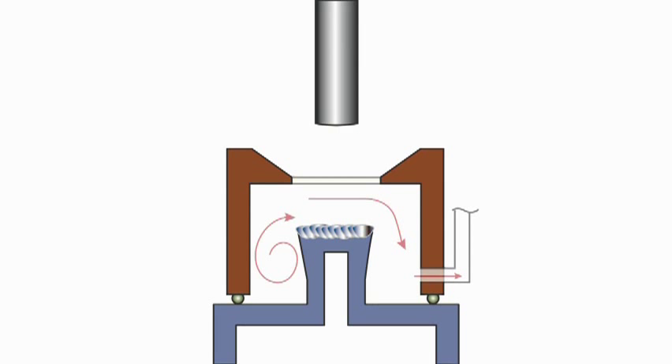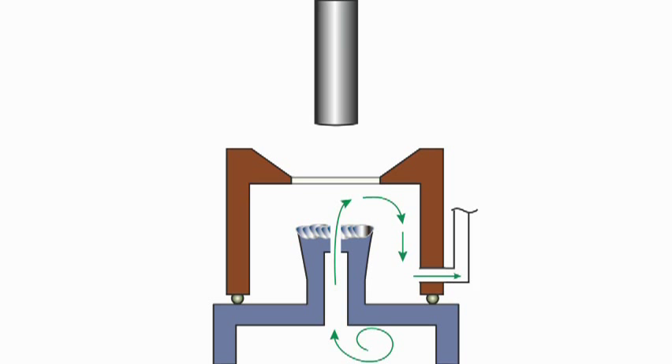The shielding gas is then removed and the manifold is evacuated to a high vacuum. The laser is focused for drilling and a hole is drilled into the container through the alloy material. With the enclosure accessed, the contents can be safely removed, analyzed, and replaced if necessary.